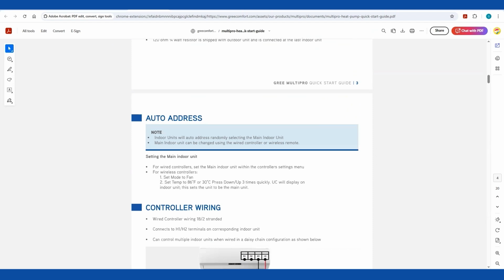Just a little refresher, the indoor units are auto address. On the wire controllers, you can set that main indoor unit. If the indoor unit is not the one you want it to be, you can go to any one of the controllers and make that unit the master or the main indoor unit. If you have a wireless controller, you set the mode to fan, set the temp to 86 degrees or 30 degrees Celsius. Press down and up 3 times quickly. UC will display on the indoor unit, and this sets the unit to the main indoor unit.